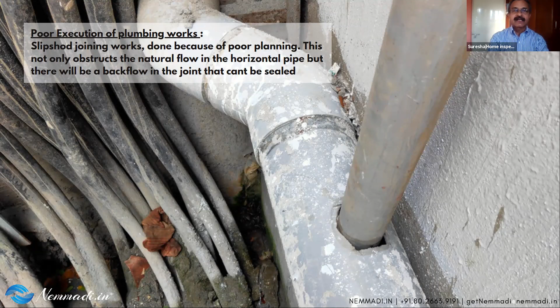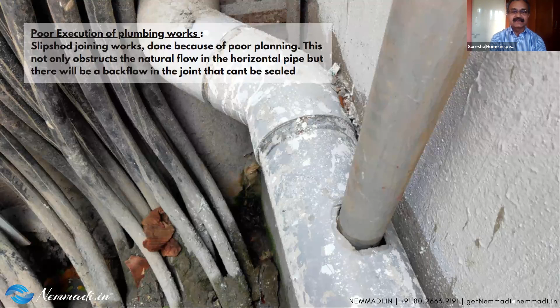This is a very classic case of what we call jugaad. There's a pipeline running below and another coming from the top, which should have been properly joined to the horizontal pipeline. But when somebody isn't careful or supervising, instead of using a standard joint, they just punched a hole and put in the pipe. In case of excess water, the whole thing overflows by the side and becomes a mess, imagine your car parked below this in a basement with dirty water overflowing like this. These are things that can only be noticed if you have an eye for detail.